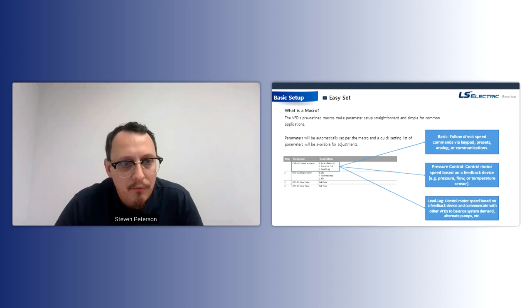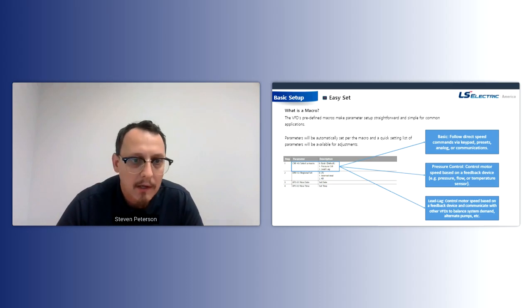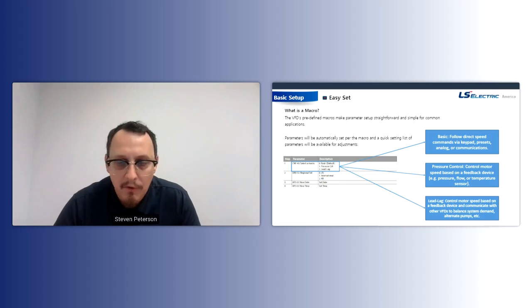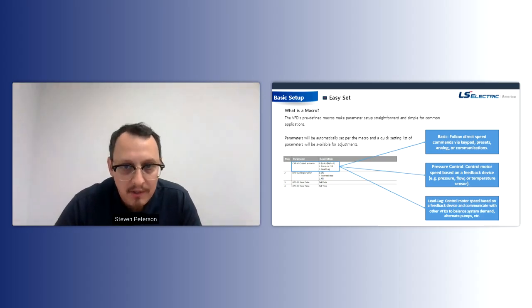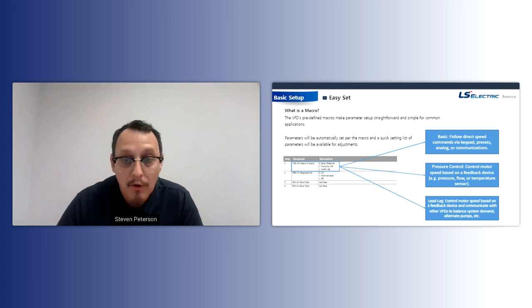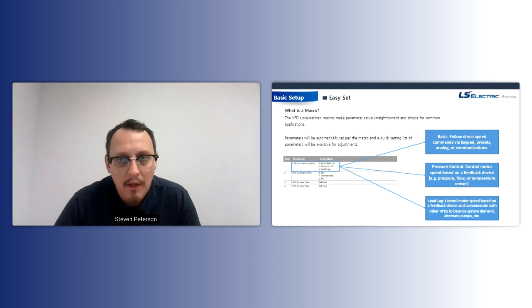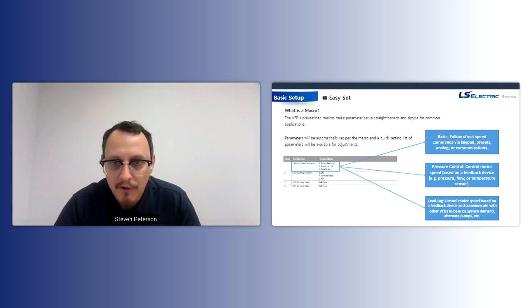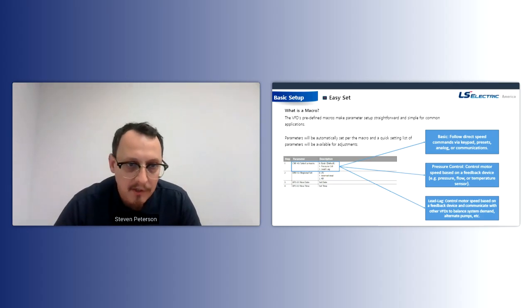So on the H100 Plus, we have 3 different macros. We have basic, pressure control, and lead lag. And we're going to be diving into each one of those. Basic is exactly as it sounds. It's a direct speed command. So that could be via keypad, presets, analog inputs, or communications. And then usually like a hardwired run stop. So if you have like a control relay that starts the drive and you have a direct 0 to 10 signal or something, that would most likely be a basic macro. So you just leave it at basic. And if you look on this table here, it says that's the default.